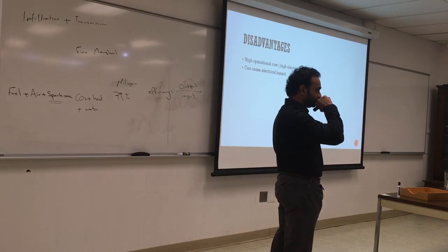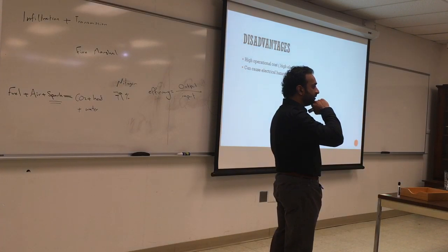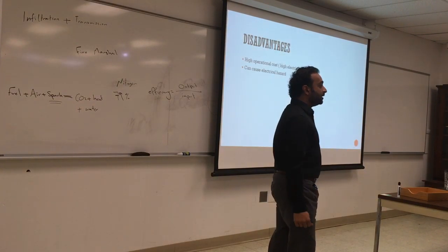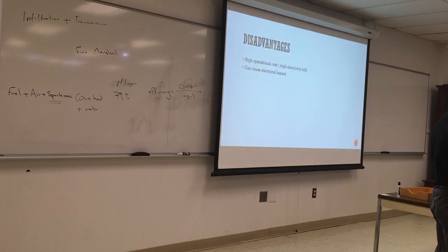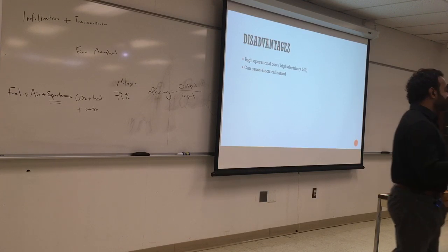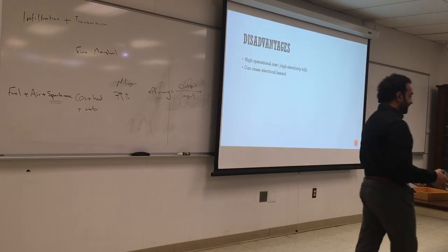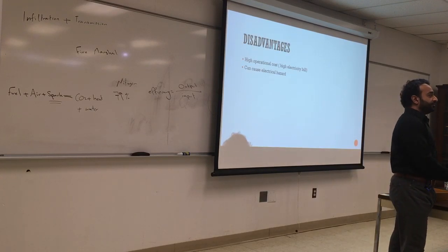Yeah. So like you were just saying, if you want to have an electrical baseboard, does an electrician have to wire the whole thing in, wire it into the panel, or can the technician do the room by room stuff? They have to do it room by room, and they have to check the circuit. They want to check what the load on the circuit is and make sure that the circuit can take that heater. Because if you have a 3 foot radiator that is electrical, they want to make sure that the amount of draw by the amperage does not exceed the circuit amperage.